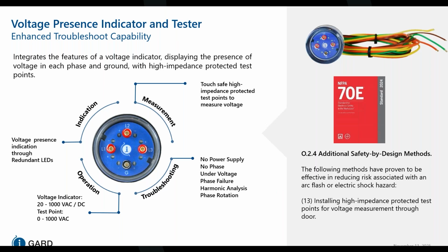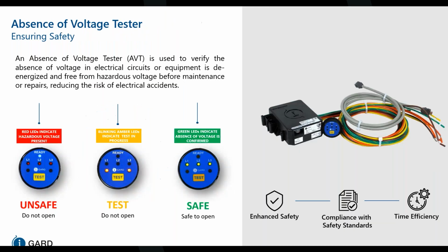NFPA 70E revision of 2024 Annex O.2.4 included the installation of absence of voltage test port under the section heading Additional Safety by Design method and recommends voltage measurement through the door using the test port. This method has proven to be effective in reducing the risk associated with arc flash or electrical shock hazards. Now let's talk about absence of voltage tester. It is used to verify the absence of voltage in electrical circuits and to see if the equipment is de-energized and free from hazardous voltage before maintenance or repair begins, reducing the risk of electrical accidents.